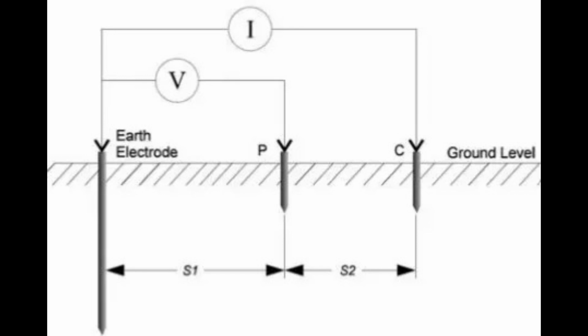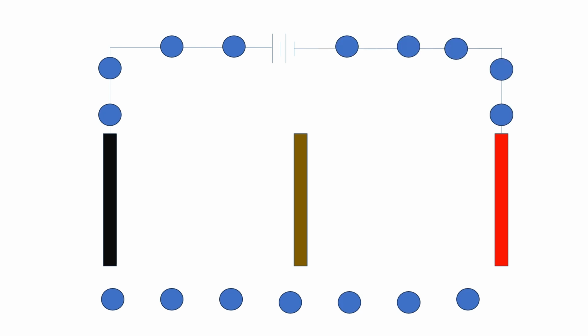An AC supply is passed between the ground and the current electrode. The potential electrode measures the voltage drop in the soil caused by the current flowing between the earth electrode and the current electrode. Hence, by using Ohm's law, we can calculate the resistance in the ground. To prove this method, we have practically implemented it, which I will show you now.